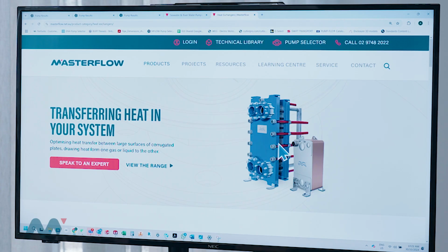That's the important thing. On the screen we have heat exchangers we sell to the market. The maximum recommended velocity going into the connections of the heat exchanger is 7 meters per second. What would be the recommendation for the velocity going into the pump suction?